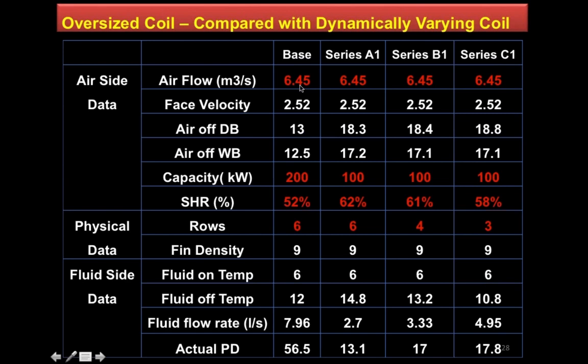A 6.45 cubic meters per second airflow, 200 kilowatts capacity. And I'm going to use the sensible heat ratio that I get from a standard coil selection program as the basis to see how I'm doing in terms of the sensible and latent cooling coil performance. So I got a 6-row deep cooling coil. When I install it, I call this the series A1, where I notice that my actual load is only 100 kilowatts. There you go, 200 oversized, 100 is what I really need at commissioning.